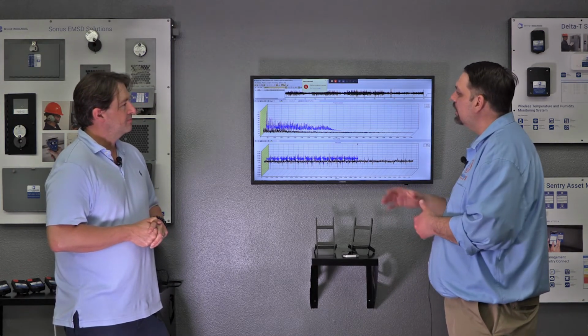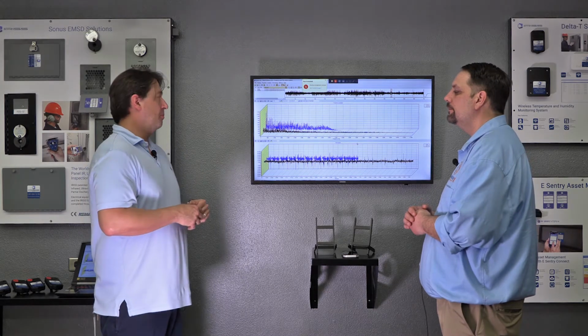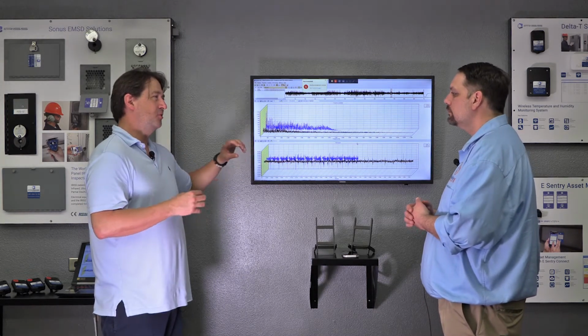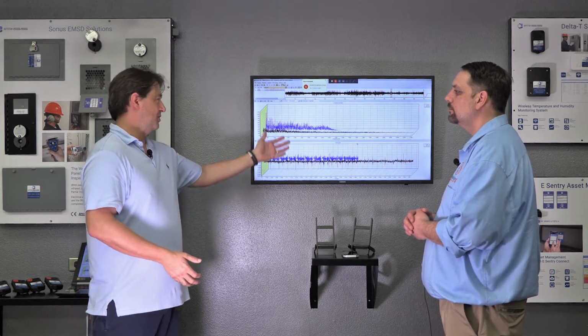So that's great. Is there anything else that this can do that stands out from everybody else? Well, as far as standing out, I just think that spectrogram surfacing is really there. There's some other plotting, some spiderweb plotting and stuff like that, but as an ultrasound enthusiast, I really find that the spectrogram surfacing is probably my favorite for reporting and showing people a wow factor. But for analysis, the time signal. I'm a huge time signal fan, because no matter what angle you're at, that event's always going to show up in a time signal in some portion, because it's not dependent on converting from a time signal to a frequency spectrum.